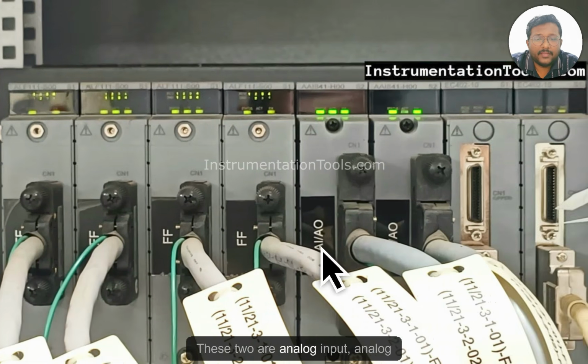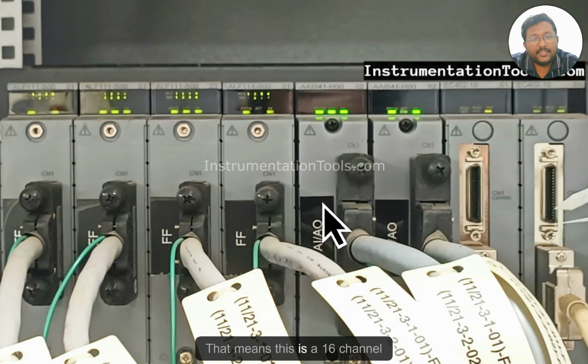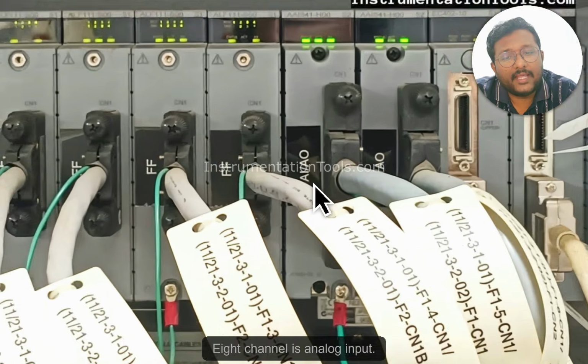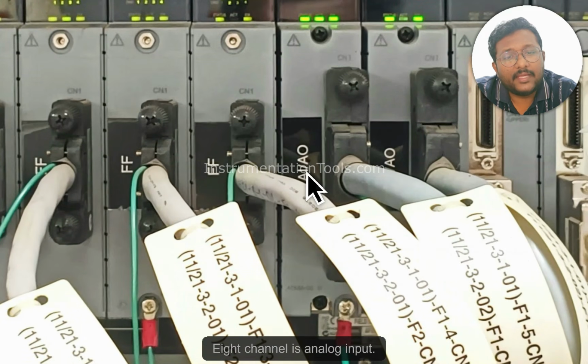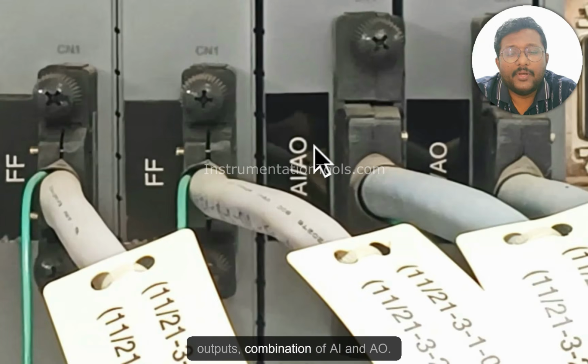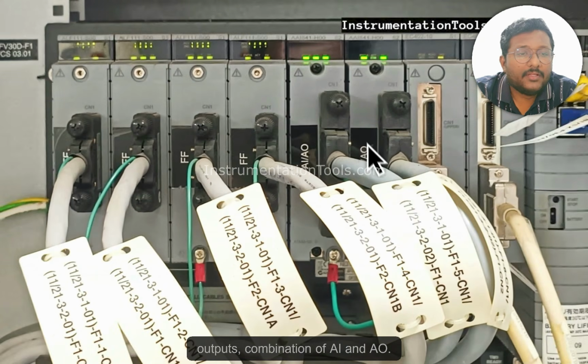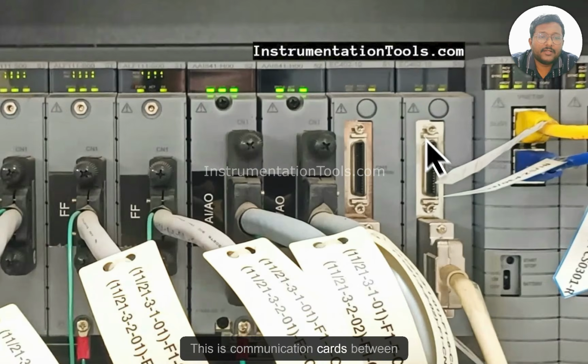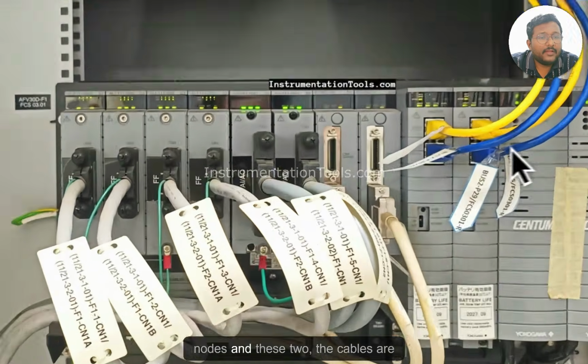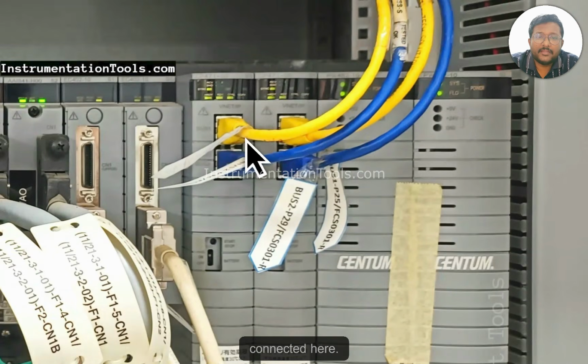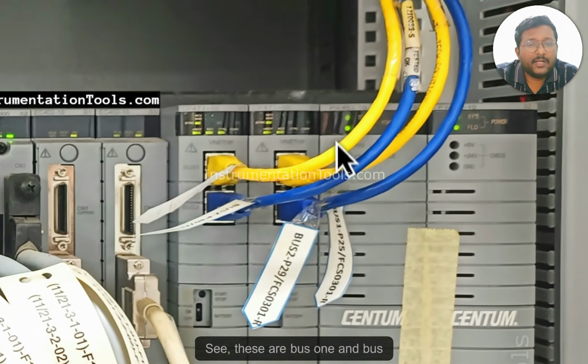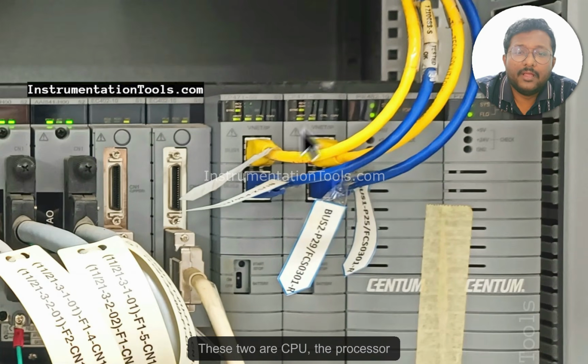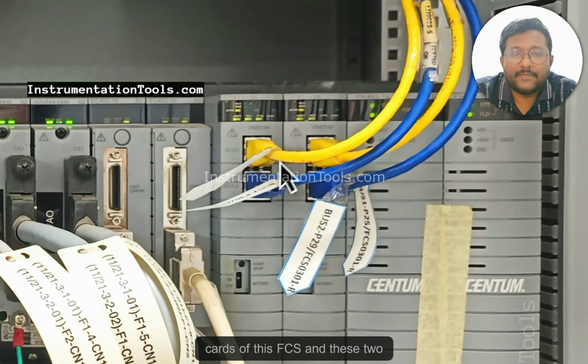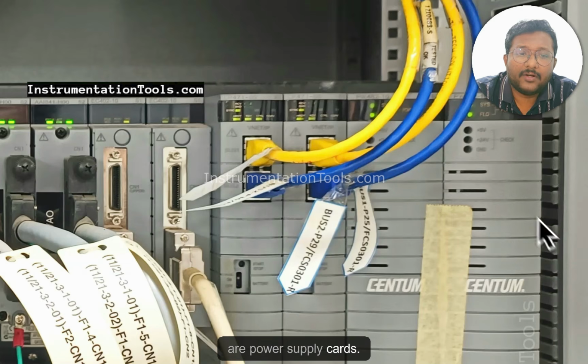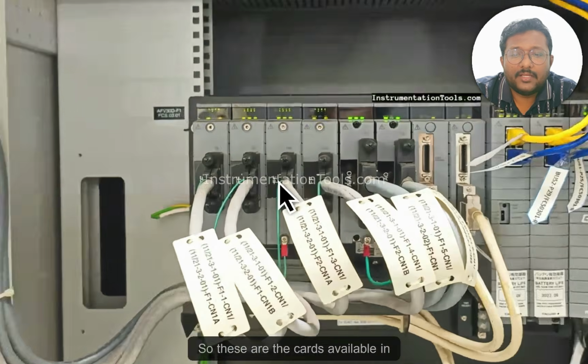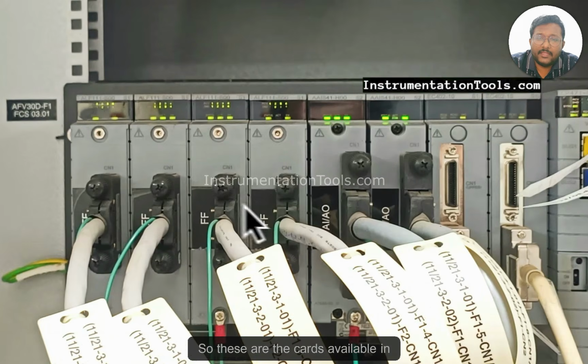These two are analog input and analog output. That means this is a 16 channel card, where 8 channels are analog inputs and the next 8 channels are analog outputs, a combination of AI and AO. This is also the same. This is the communication card between nodes, and the cables are connected here. See, these are bus 1 and bus 2. These two are the CPUs, the processor cards of this FCS, and these two are power supply cards. So these are the cards available in the system cabinet.